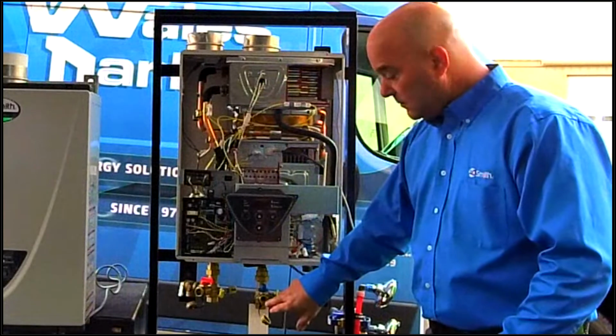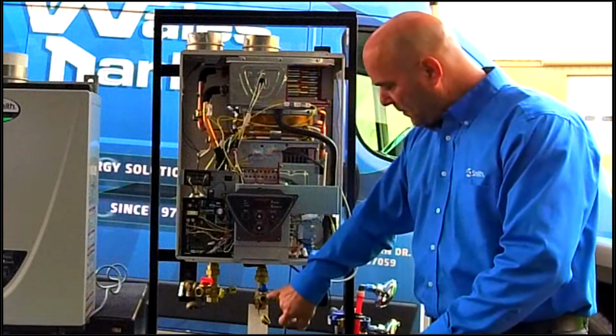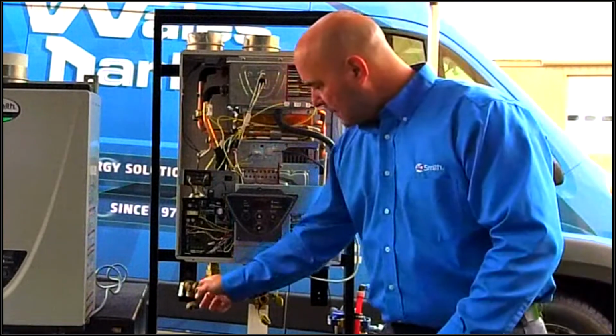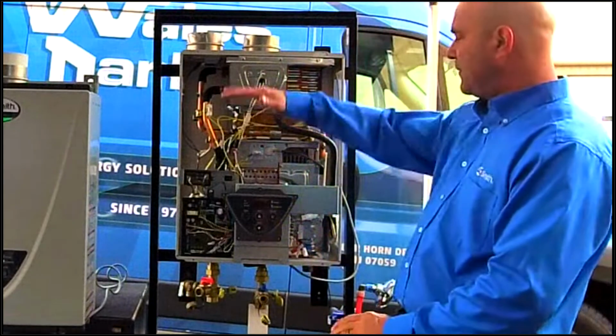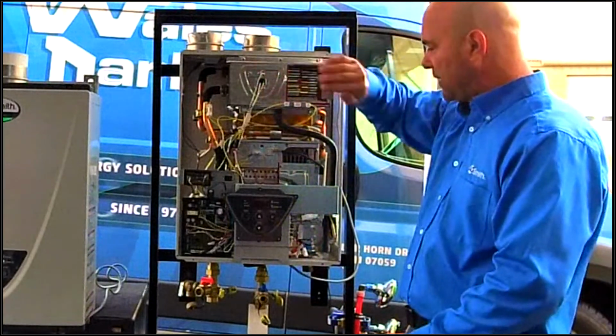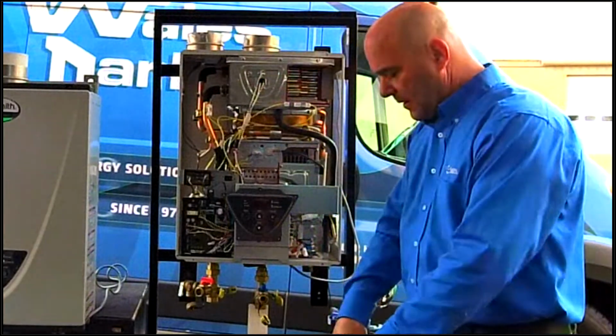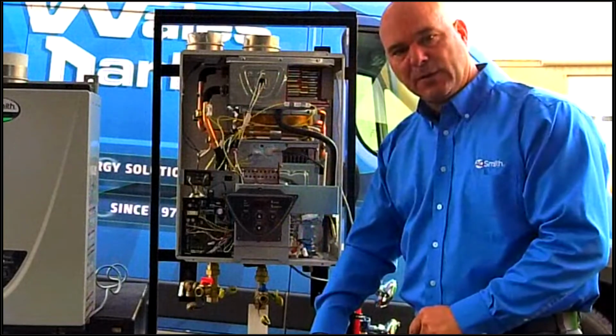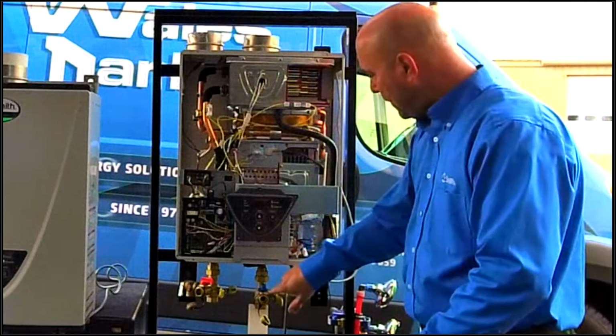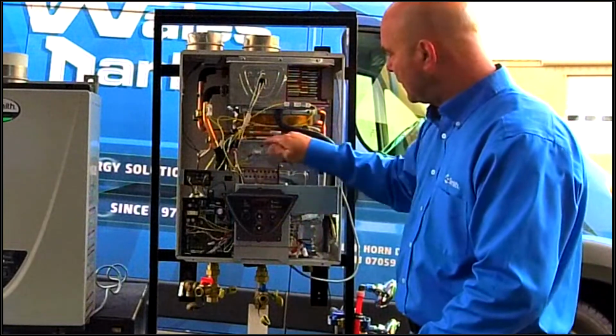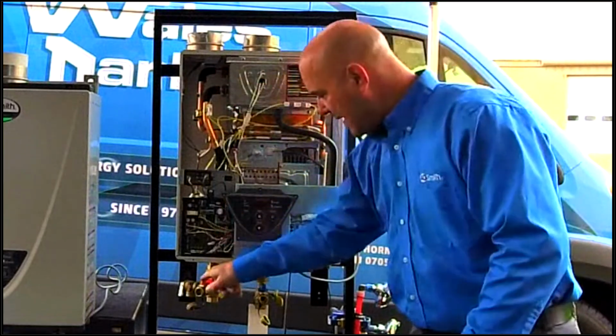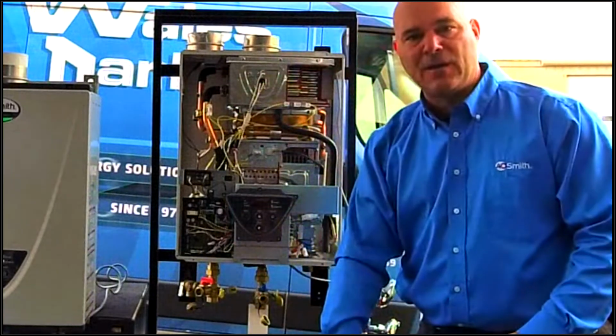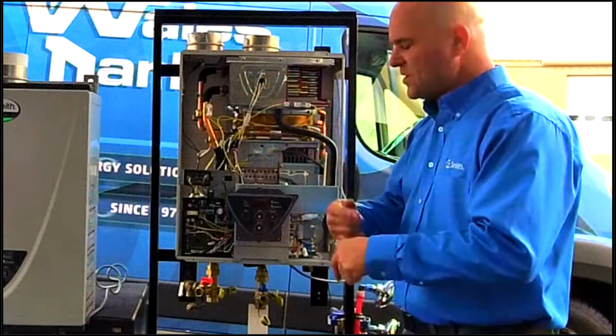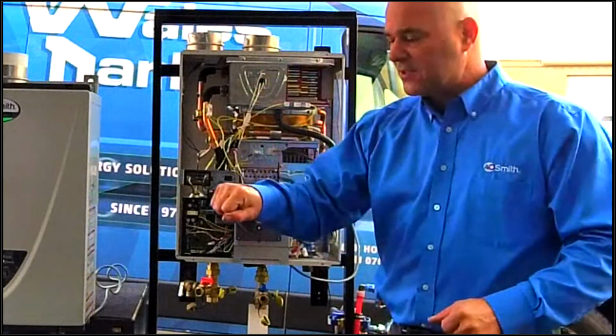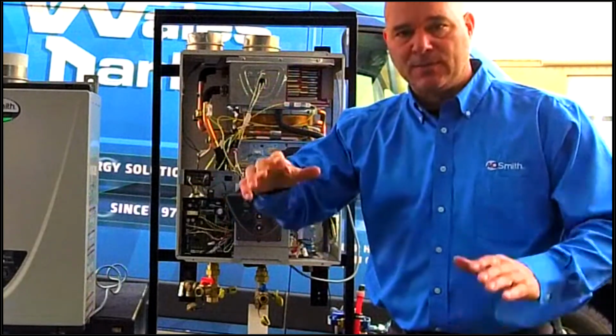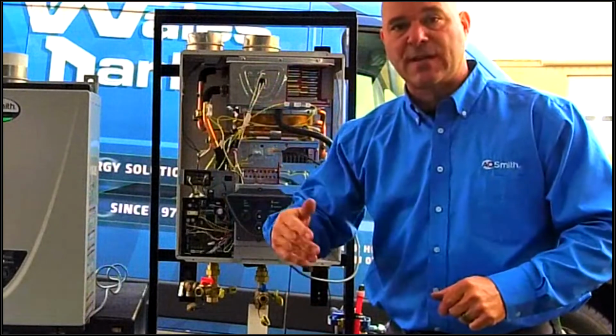I have my hose with my pump going to my cold, and then I'm coming back out. I've already elevated it to 140 degrees. I've shut it off. I'm now going to turn my pump on with that little bit of water, and I'm going to start to flow the water in the cold up through the heat exchangers, back down, and out back into the bucket. And once I get that flow going, then I'm going to start to add my chemical, whatever it might be, whatever your chemical of choice is.